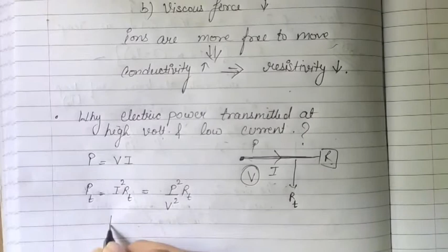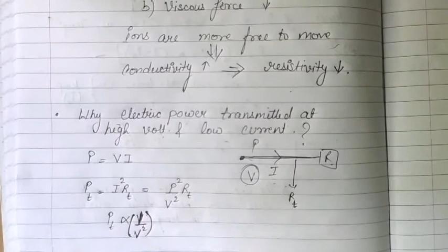So the power wasted in the transmission cable is inversely proportional to the square of the voltage, that is, P_T is proportional to 1 upon V squared. So to minimize the power loss, the electric power is transmitted at high voltages and low currents, meaning if we keep the voltage high, this value P_T will be minimum.